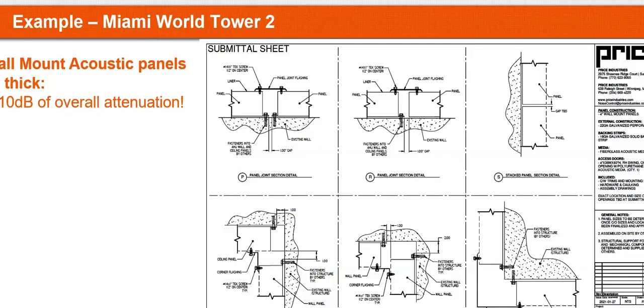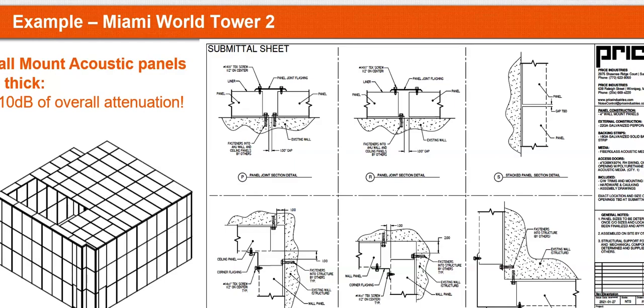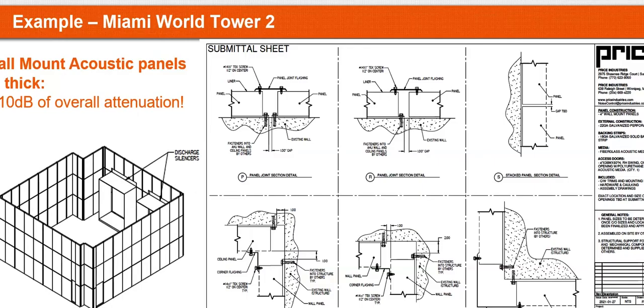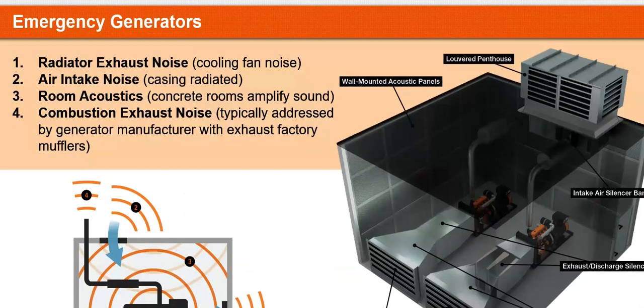So what that means is when you add absorptivity, you can now start using a little bit of your distance effect to the openings. We do a good job at giving you the panel layout so that you know where you can add conduit, where the openings can be, but this is just a quick example of the typical connection details where you could start adding wall mount panels into a very noisy generator room to start with. So if it's a retrofit application, the first step would be to add absorption to the walls. This is the typical solution aside from the combustion exhaust muffler that typically comes already sized by the generator manufacturer. You have your silencers for air to come in so that these diesel generators can operate, so they can combust and then start generating power.